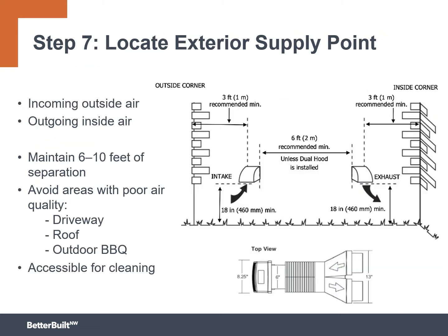Next up, let's locate our exterior supply and exhaust points. So we want to be thinking about both the incoming outside air as well as the outgoing inside air. Ideally, we want to maintain 6 to 10 feet between the two. This helps to make sure that the air that we just exhausted out of the house doesn't get sucked right back in. That doesn't do us too many favors for our indoor environmental quality.